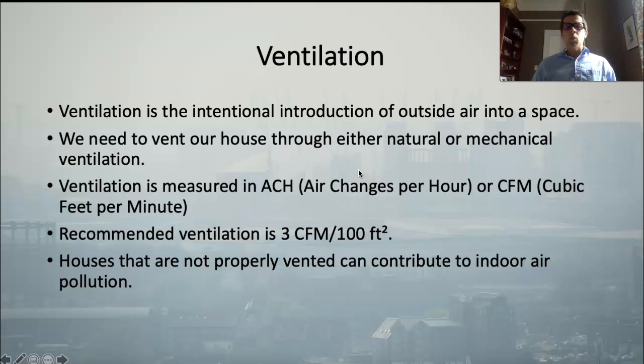When we talk about ventilation, we're talking about air changes per hour, how many times the air in the house is completely replaced, or cubic feet per minute. How many cubic feet of air are being displaced and replaced per minute? The recommended amount of ventilation is 3 cubic feet per minute for every 100 square feet of the space.